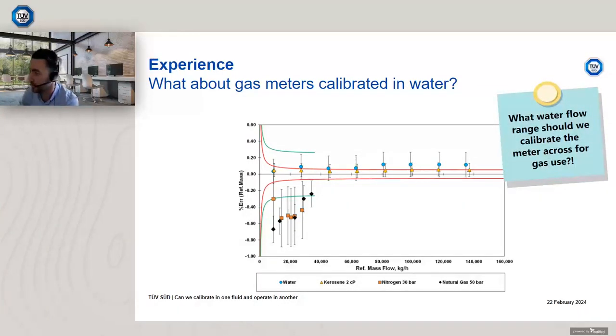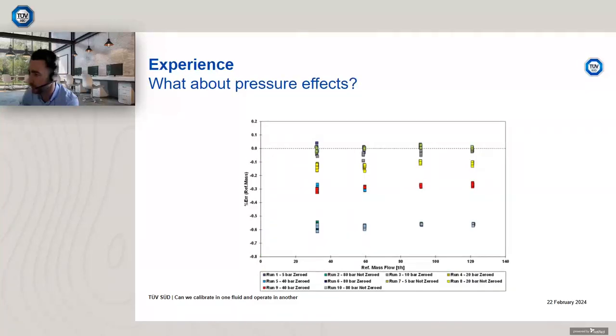So that's gas, and I started to mention the slight effect there of pressure. So what about the pressure effect? So this again is a Coriolis meter, and you can see I'm showing a lot of data here, 10 separate calibrations. In this case I've named them as runs, from nominally 5 bar up to 80 bar, and I've also differed between whether I zeroed the device or didn't zero the device. The zero, in this case for this manufacturer, in this model type, the zero at pressure didn't appear to have an effect. So there wasn't a large effect with respect to the zero value that was recorded, whether we were at high or low pressure.